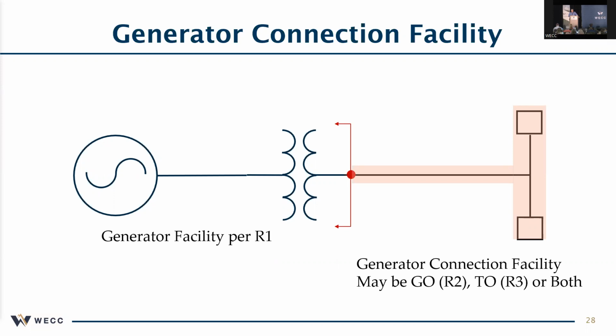so that that whole generator connection can be an accurate and complete facility rating. Now, this is a case where WECC is not necessarily in full alignment with the rest of the regions. The regions don't have a huge problem with this, but in some cases they will allow more flexibility and say, if they only want to go up to the bus and not include the breakers, they'll allow that flexibility in some cases. We're not at this time. So that's the way it is. We've talked about it. We've thought, hey, what are the pros and cons of doing it? And at this time, this is our perspective on it.